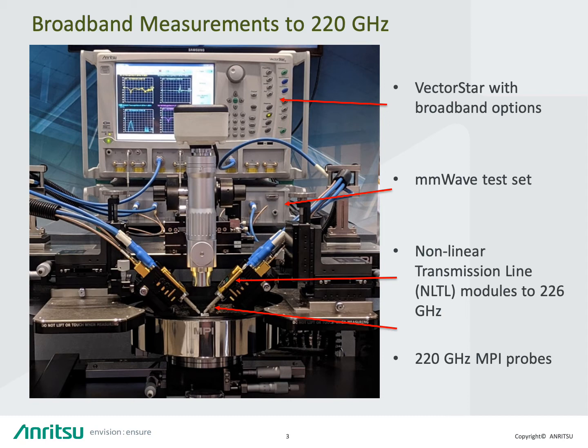So the VectorStar in this case is sweeping from 70 kilohertz to 54 gigahertz and then switching over to the mmWave test set. The mmWave test set routes the RF and LO signals to the nonlinear transmission line modules, which then provide measurements up to 226 gigahertz. And that module is connected to the probes, which then provide the on-wafer measurement capabilities.